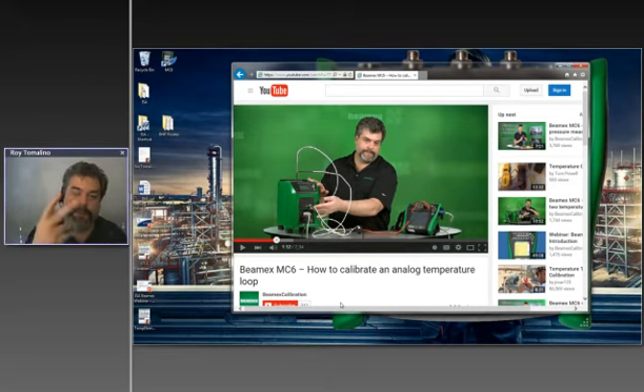In this case, we have a temperature transmitter. This one happens to be HART, so we want our 4 to 20 output. And it's a loop because we have our temperature probe plugged into the dry block that you can see, and that's connected to our transmitter, which gives us our 4 to 20 milliamp output. So we're literally testing the temperature on the input, and then we're comparing that against the milliamp output to see if there's any error that needs to be adjusted.